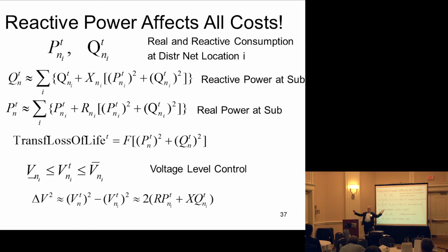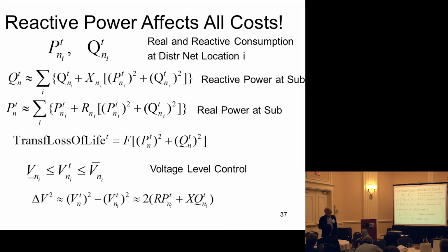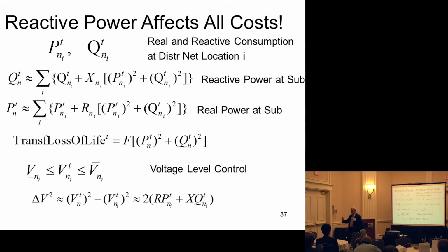And in order to have good quality, we need to maintain voltage, right? You don't want your lights to start becoming yellow, or the voltage to increase more than 6 or 7% above the rated capacity, because your appliances start getting damaged from that point on, and so on and so forth. Your refrigerator doesn't work properly. So you need to do voltage control. And voltage control, the fall in voltage, is also a function of reactive power. So you can increase the voltage by producing reactive power. You decrease the voltage by consuming reactive power, right?